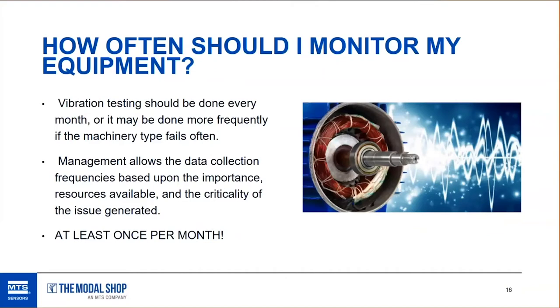How often should you monitor your equipment? The answer varies — it all goes back to money. Plants with dedicated vibration groups try to monitor once a month, though depending on the number of points, you sometimes see it slip to 60 or 90 days, once a quarter, or even once a year. Managers set collection frequencies based on importance, criticality of equipment, and budget. Bottom line: when starting or building a program, you need to look at equipment at least once per month.